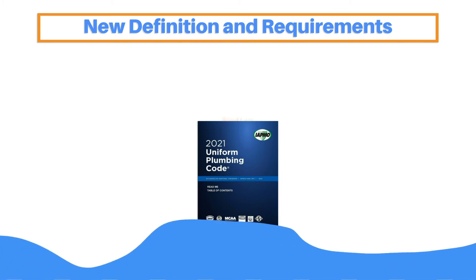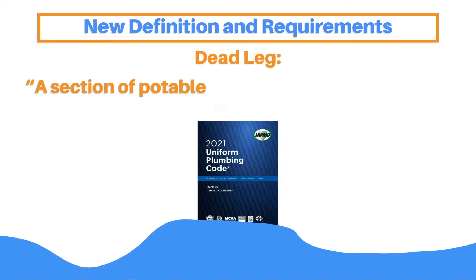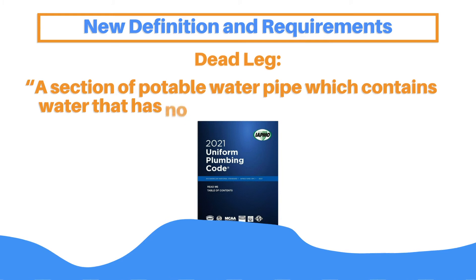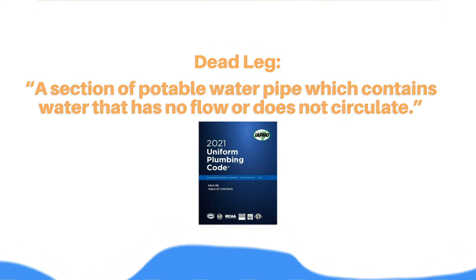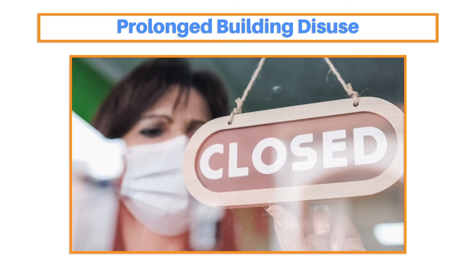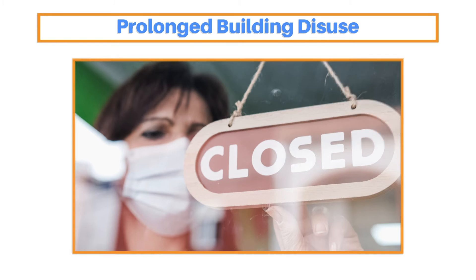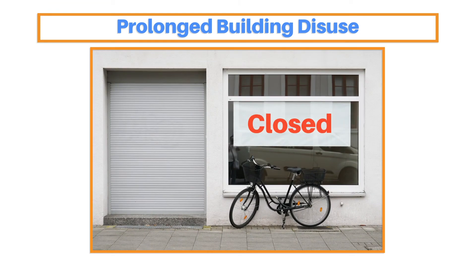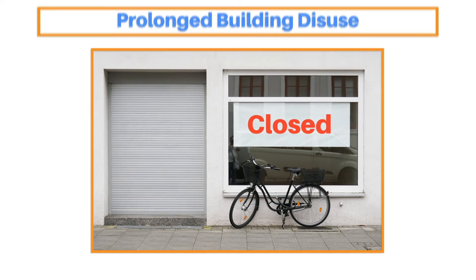The 2021 UPC defines a dead leg as a section of potable water pipe which contains water that has no flow or does not circulate. This lack of flow or circulation can happen for many reasons, but one that has become much more common recently has been prolonged building disuse due to lockdown from the COVID-19 pandemic. No matter the cause, when a building is shut down or sees a reduction in operation with significant changes in normal water use, there is the potential for serious health risks to occupants once they return to these buildings.